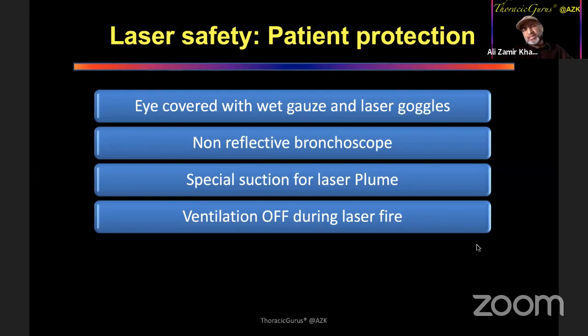And the most important thing, this is the most vital thing: there is actually a key on the laser machine. Until and unless I say "ventilation off, off," theater personnel will not turn on the key. This is the most protective method that you should use. When you turn on the key, that is the only time that you can fire the laser. Before that, you can press the foot pedal as much as you like, but the laser will not fire because the key is off. The moment I say "ventilation off, off," the anesthetist has to tell me back "ventilation off, off." Until the anesthetist tells me that the ventilation is off, that key will not go on. And then I will be able to fire.